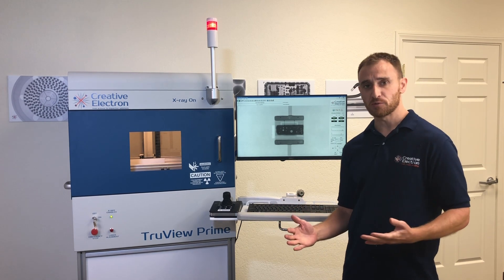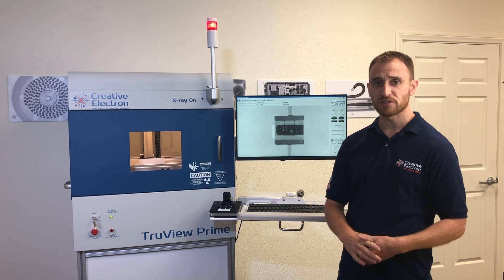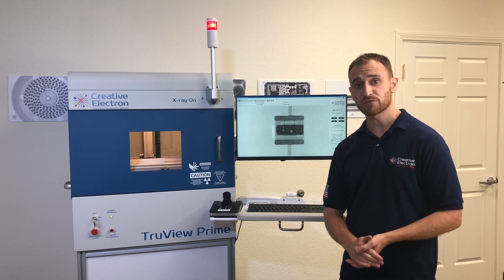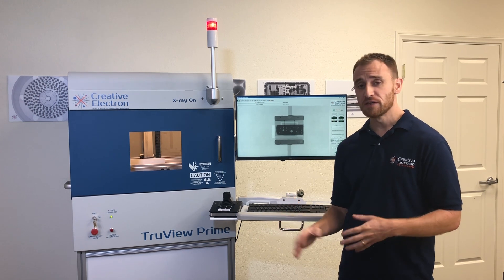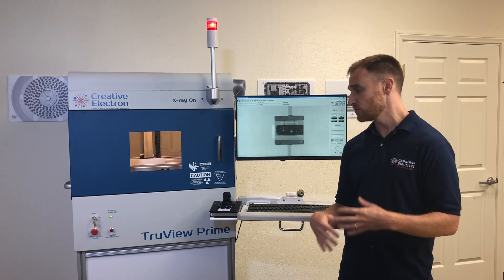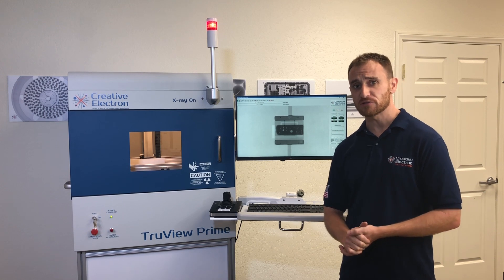The TruView Prime is configurable with several different x-ray sources ranging from the 80 kV mini focus source up to the 130 kV micro focus source. Because of that variability, the system can weigh up to 800 pounds, so we always recommend using a bench that supports at least 1,000 but preferably 2,000 pounds for safety concerns.